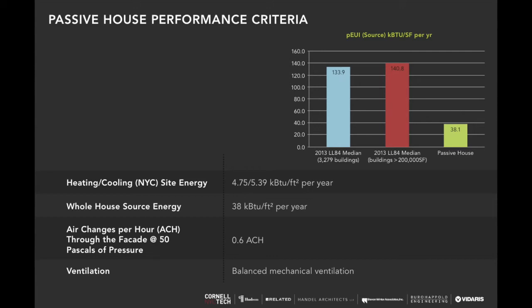This is a projected energy use intensity. EUI — energy use intensity from the source — is defined as thousands of BTUs per square foot per year of primary energy consumption to support all activity in the building. Within that total budget, you're given some for heating and some for cooling, and that's really the heart of what Passive House is all about. They really stress the importance of airtightness. It's intuitive: BTUs equals CFM times delta-T times 1.08. When you look at it that way, every CFM of unintended air movement is a huge energy penalty — something we've just lived with in the built environment for a really long time.